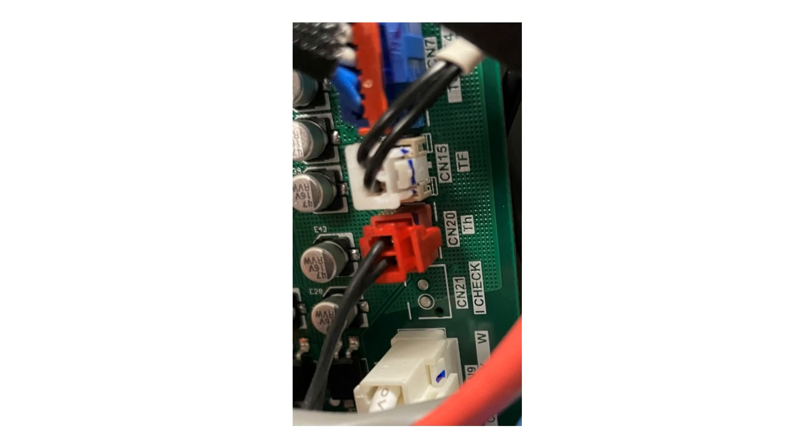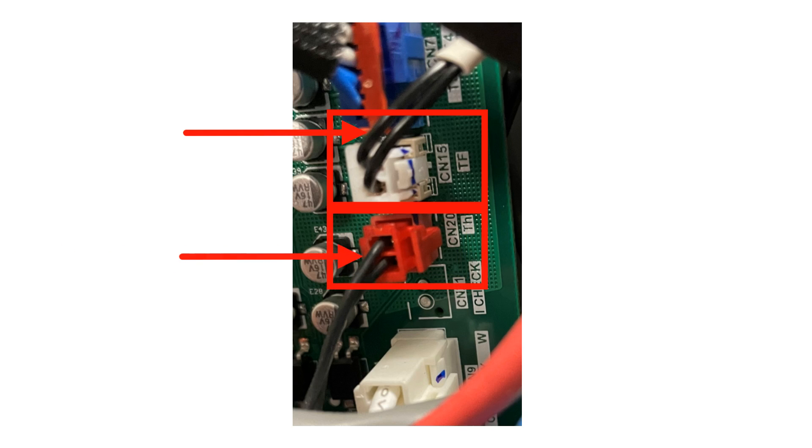Now, remove the white plug and use your leads to test across the two black wires for the TF sensor. Write down this value. Lastly, remove the red plug and test across the two black wires for the TH sensor. Write down this value.